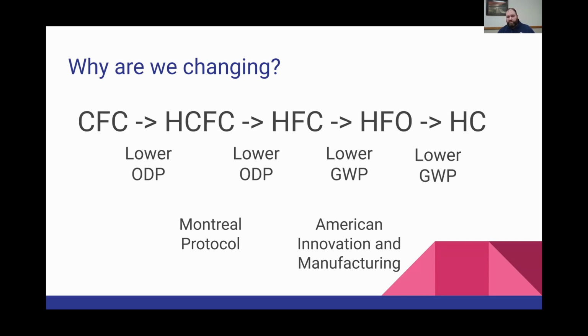Both of those shifts were driven by lowering the ODP, the ozone depletion potential. CFCs and HCFCs both have chlorine in them. Chlorine was identified as a compound that could cause ozone depletion. HFCs have no chlorine, therefore they have no ODP value. It was identified that they still had a global warming potential, and so the American Innovation and Manufacturing Act said, let's start moving towards something with even lower global warming potentials. So now we're seeing the phase out of R134A in automotive and commercial industrial HVAC, and R410A, which for the last 15 years was our primary refrigerant used in residential systems.